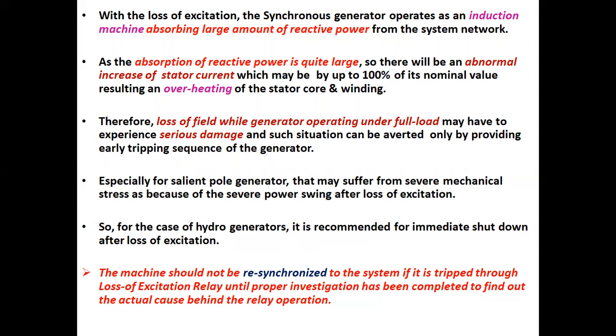Specially for salient pole generators, which may suffer from severe mechanical stress because of severe power swings after loss of excitation, for the case of hydro generators it is recommended for immediate shutdown after loss of excitation. The machine should not be resynchronized to the system if it is tripped through the loss of excitation relay, until a proper investigation has been completed to find out the actual cause behind the relay operation.